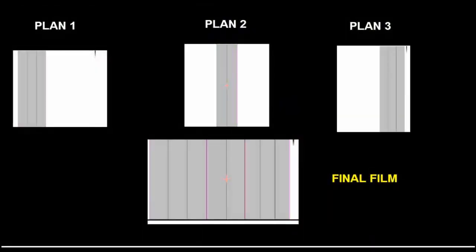In summary: from plan 1 we get three strips — strip 1, 2, and 3. From plan 2 we get strip 4 and strip 5. From plan 3 we get three strips — strip 6, 7, and 8. When we view all three plans on a single film, we get eight strips in total. This is the picket fence test, in which you will get eight strips.